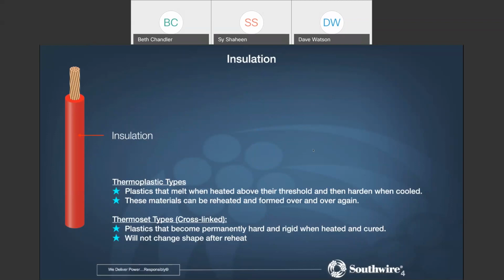Now, what does this mean? If you overstress the insulation, if you go above the maximum temperature on a thermoplastic type product, the insulation will deform and then potentially melt off of the conductor. With the thermoset, or cross-linked conductors, these are plastics that are going to become permanently hard and rigid when heated and cured. In other words, they're going to char and stay in place rather than deforming and melting off of the conductor. So they're not going to change shape after the reheat. Now, next slide.